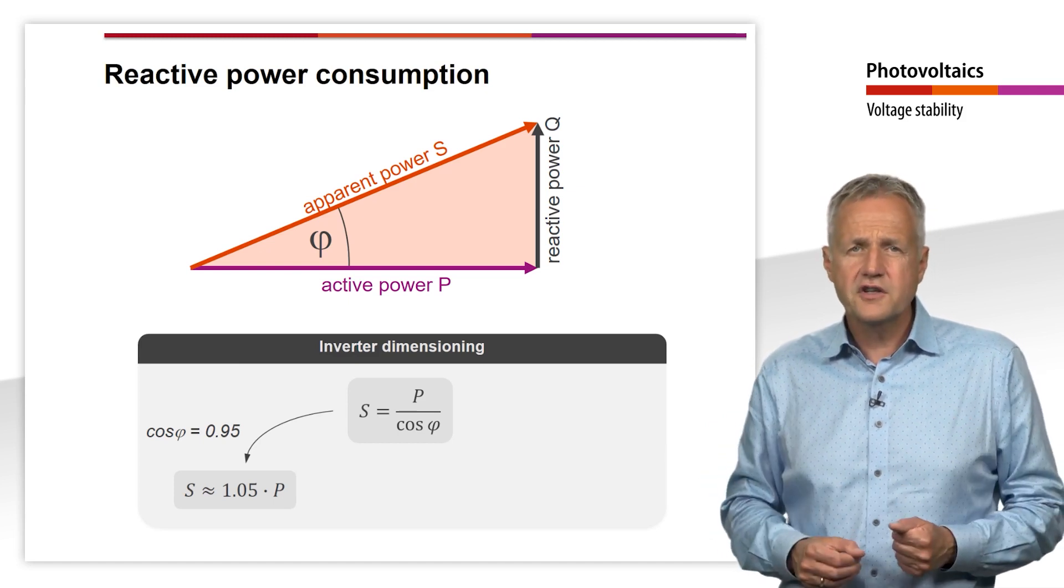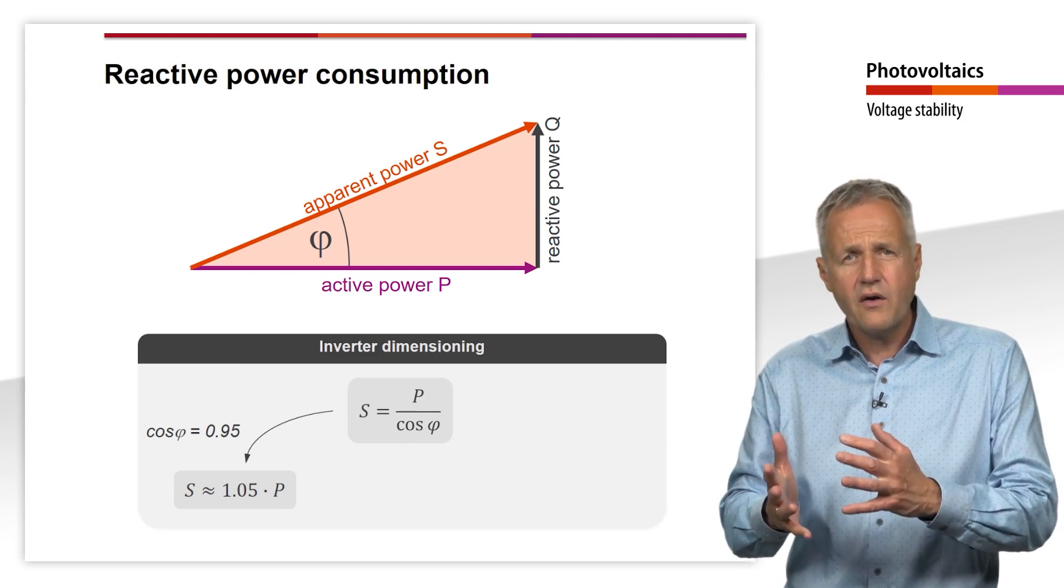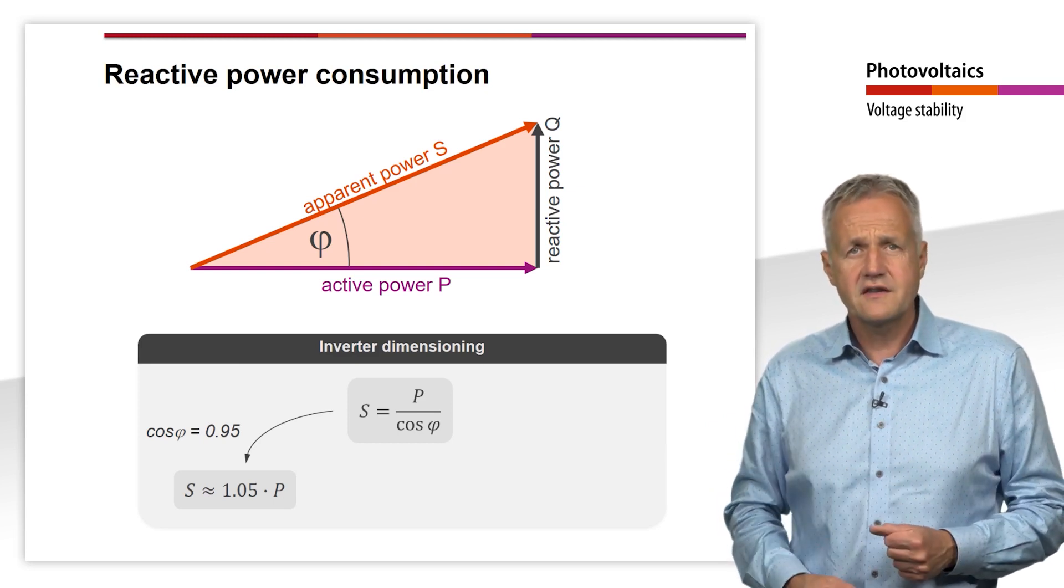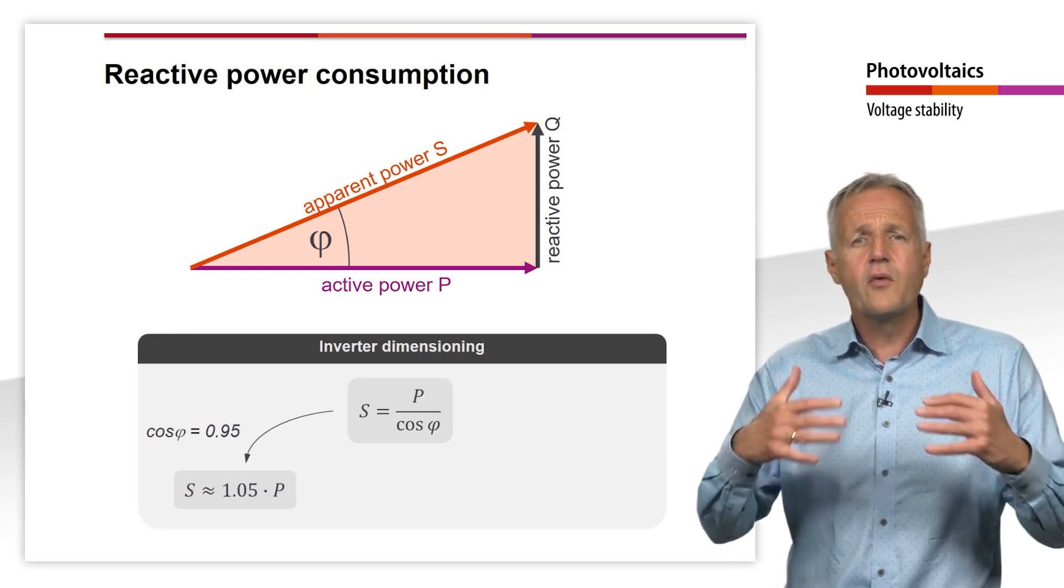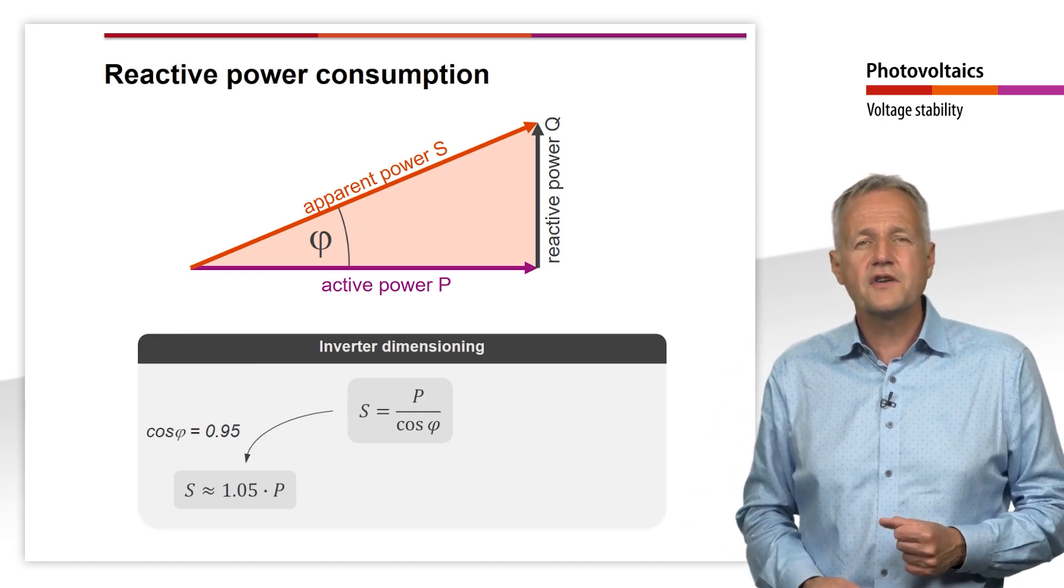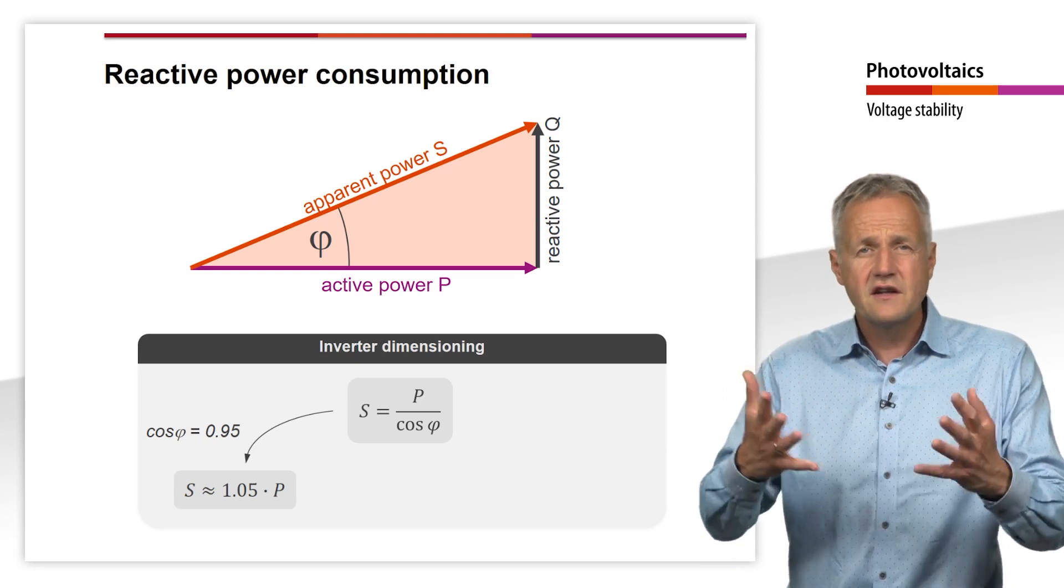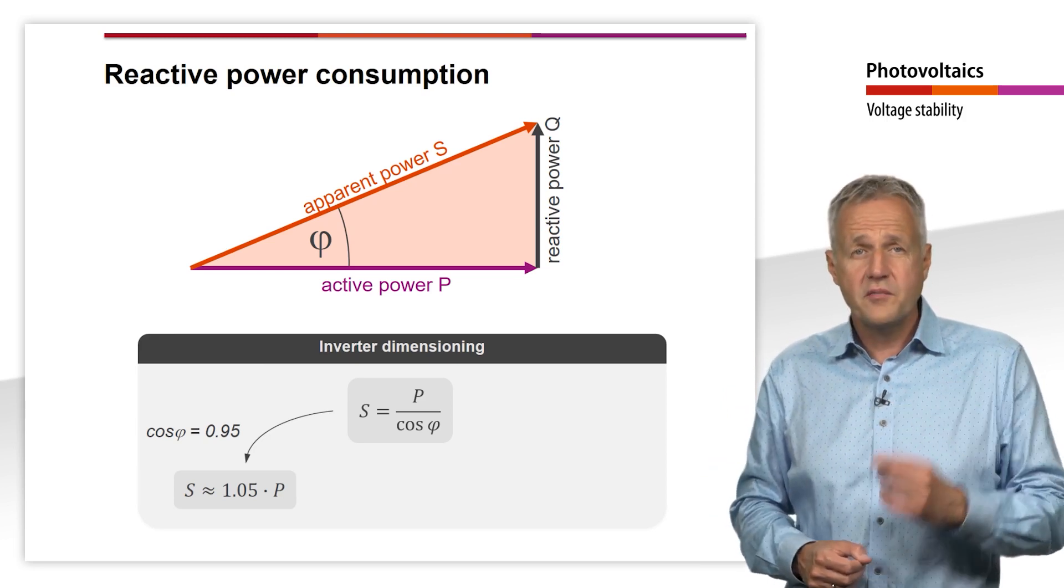For the dimensioning of the inverter, it is not the active power but the apparent power that is decisive. The inverter must therefore be designed a little more than 5% larger in order to be able to feed in the required reactive power.